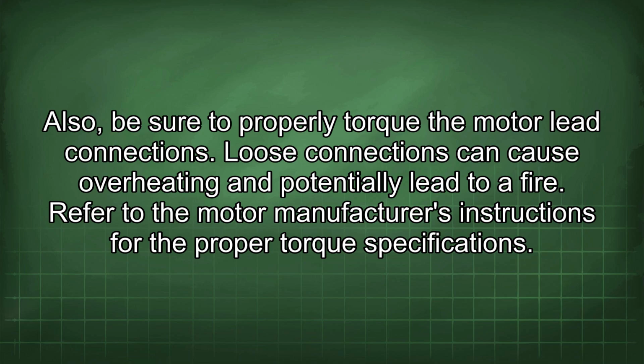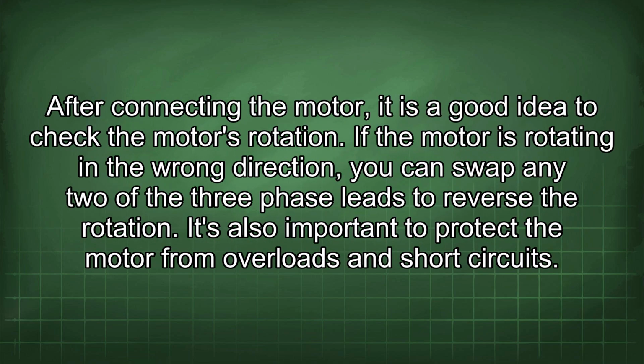Also, be sure to properly torque the motor lead connections. Loose connections can cause overheating and potentially lead to a fire. Refer to the motor manufacturer's instructions for the proper torque specifications. After connecting the motor, it is a good idea to check the motor's rotation. If the motor is rotating in the wrong direction, you can swap any two of the three-phase leads to reverse the rotation. It's also important to protect the motor from overloads and short circuits.